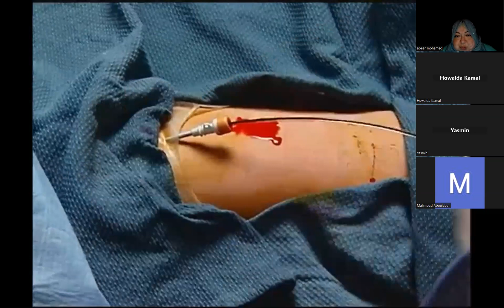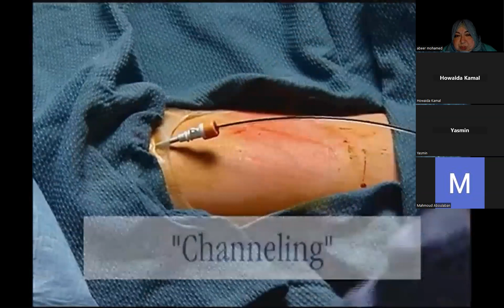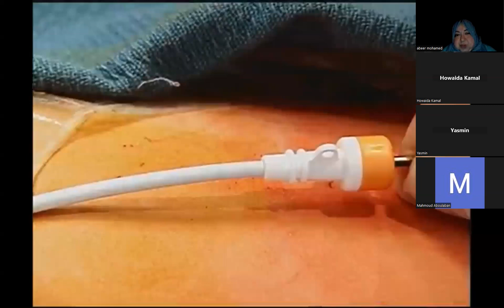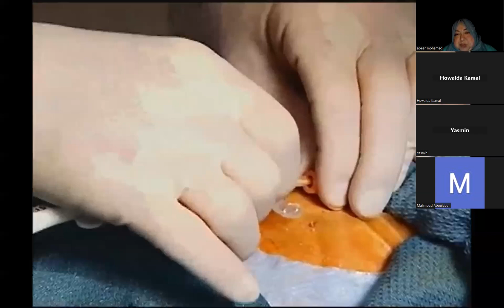Thus, at this stage of sheathed insertion, bleeding from the folds at the membrane catheter junction may be observed. This phenomenon, called channeling, is not a leak. It will stop as soon as the balloon membrane is fully advanced into the sheath. Position the balloon catheter in the manner reviewed in the sheathless insertion. Once proper balloon position is confirmed, if the first single catheter marking is visible, withdraw the 6-inch sheath past it. This ensures that the balloon membrane has fully exited the sheath and will inflate properly. Advance the movable sheath seal until it engages the hemostasis valve. The StatGuard sleeve allows repositioning of the balloon if necessary.